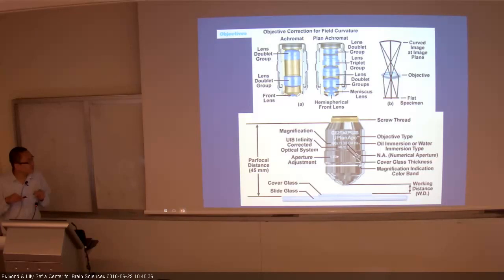Then the second important thing is magnification. This magnification is only meaningful if you put this objective in the infinity corrected microscope. If you put it in a different design microscope, it can be different, so you get a different size image. Just keep that in mind. Next, oil immersion or water immersion. If it says oil, then it's oil. Sometimes water is short for just a W, and then it's water. That's the important thing you need to know. And the other is air. When it doesn't say anything, it can be just air, or there are other labels.